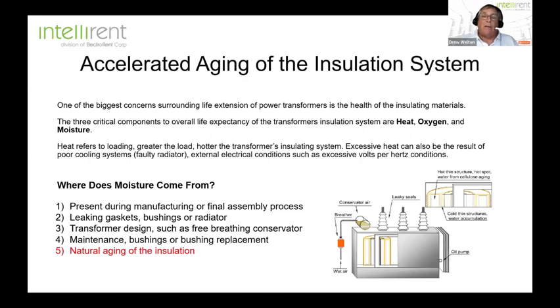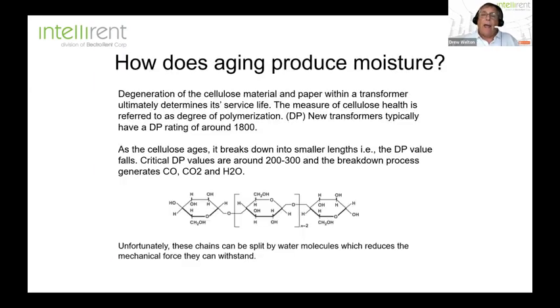But the one thing that I think is most important to understand is that moisture comes from the natural aging of the insulating system itself. The solid insulation is made up of paper, pressboard, and also polymers and cellulose in the cellulose paper. We have to make sure that it has a good degree of polymerization, or DP. That's the strength of the insulating paper in the transformer itself, and a good, healthy, brand new transformer has a measured DP rating of around 1800.